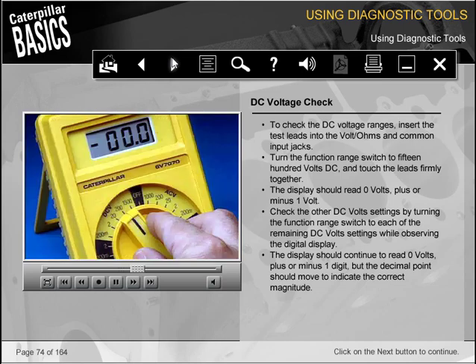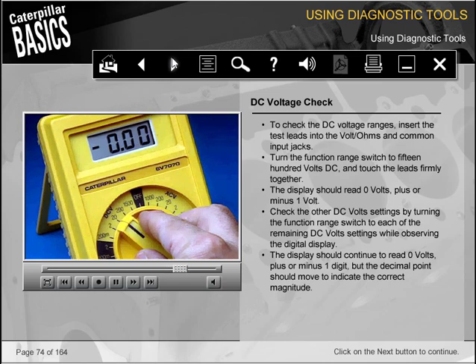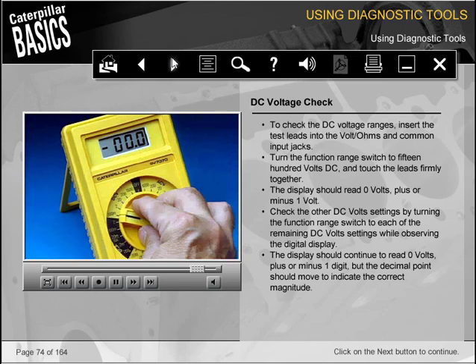Check the other DC volts settings by turning the function range switch to each of the remaining DC volts settings while observing the digital display. The display should continue to read 0 volts, plus or minus 1 digit. But the decimal point should move to indicate the correct magnitude.